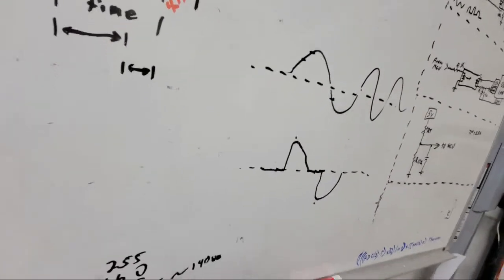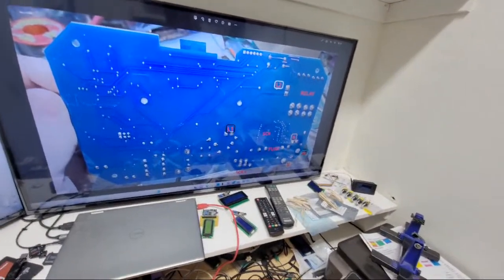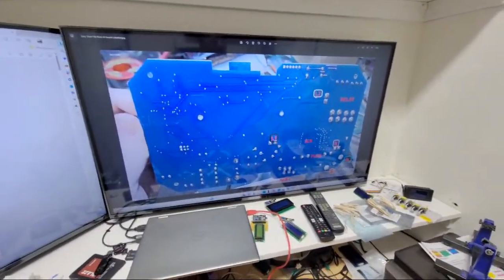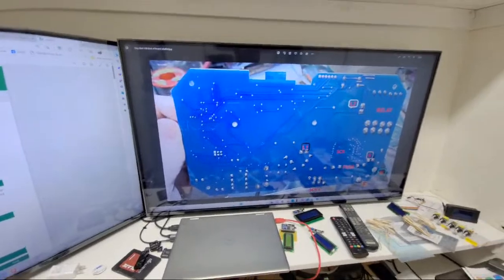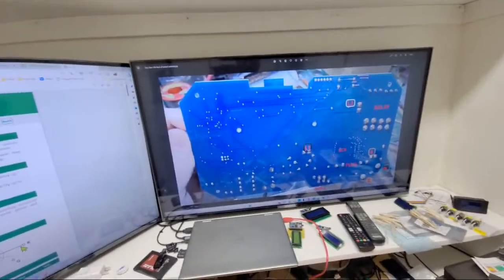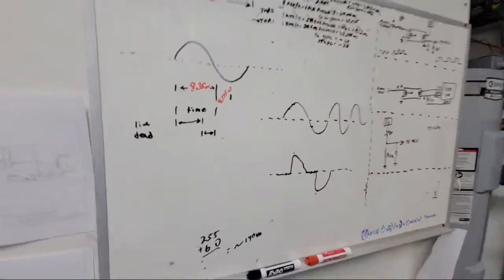It's full current. That's why if you ever put an amp probe across an outdoor fan motor with one of those ICMs on there, it never drops your current — the RMS actually seems higher. That's because the motor's speed never catches up to the 60 hertz; you're just chopping off the beginning of the sine wave to slow the motor down.